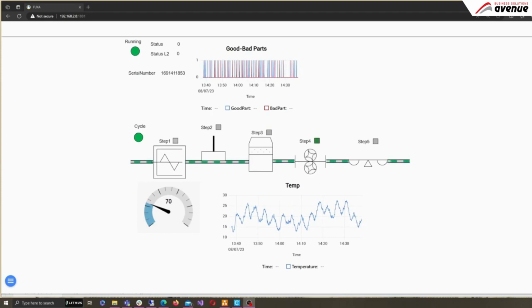As you can see in this illustration, there are multiple events. Let's take the line status. If the status shows running and the value is 1, when it's green, the line is operational. If red and 0, then it's a downtime. So the very first event is triggered when the signal goes from 1 to 0. And it ends when the signal goes back from 0 to 1 again. This event tells us about a potential downtime.